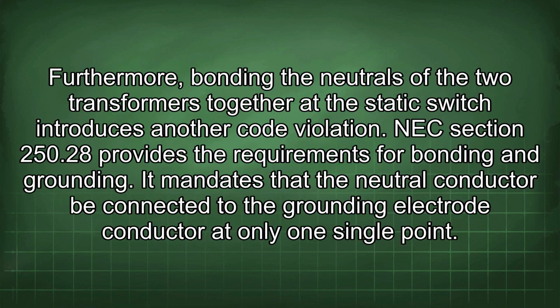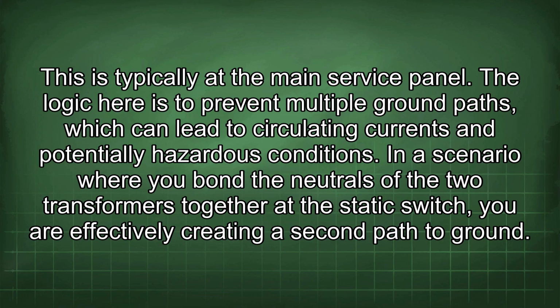Furthermore, bonding the neutrals of the two transformers together at the static switch introduces another code violation. NEC Section 250.28 provides the requirements for bonding and grounding. It mandates that the neutral conductor be connected to the grounding electrode conductor at only one single point. This is typically at the main service panel. The logic here is to prevent multiple ground paths, which can lead to circulating currents and potentially hazardous conditions.